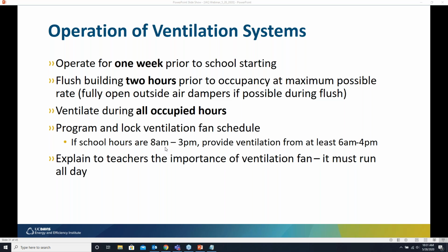So for example, if your school hours are 8 a.m. to 3 p.m., you need to start your ventilation system at 6 a.m. And then you need to run it until the school is not occupied anymore, leaving some time for teachers and students to finish things at the end of the day, and shutting off at say 4 p.m. It's really important to explain to teachers the purpose of the ventilation fan and that it must run all day and that it's bringing in outdoor air. A lot of times it's not understood, like when the heating and cooling isn't on, why is this fan still on? That really needs to be explained so teachers understand that this is really a benefit to them and a safety concern, because it can be a bit of a nuisance. I think it's better accepted when it's understood that it has a purpose.